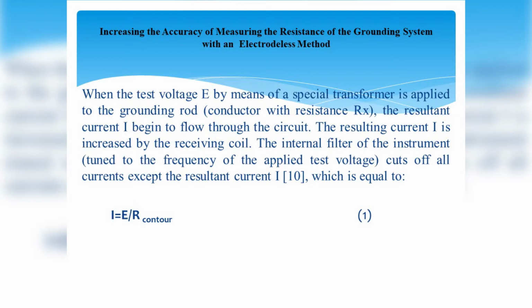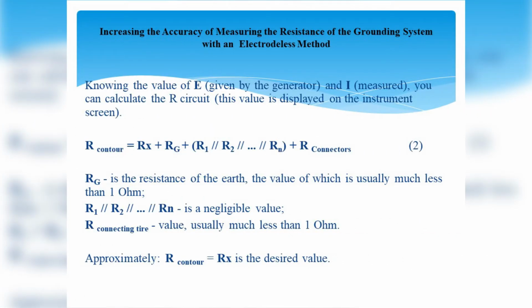The resulting current I is increased by the receiving coil. The internal filter of the instrument, tuned to the frequency of the applied test voltage, cuts off all currents except the resultant current I, which is equal to I = E / R contour. Knowing the value of E, which is given by the generator, and I, which is measured, we can calculate the R circuit. This value is displayed on the screen.